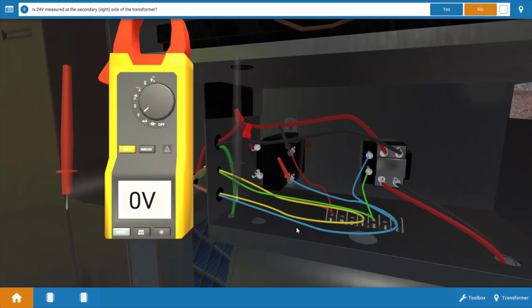One thing I would suggest prior to replacing it is turning the power off and doing a simple resistance check of each side of the transformer. Sometimes in older equipment that were not fused in the secondary circuit, a short in one of the relay coils could overload the transformer and burn the secondary winding open. And replacing it is just going to result in the same thing happening again. So after you've made these simple checks, you can then proceed on.